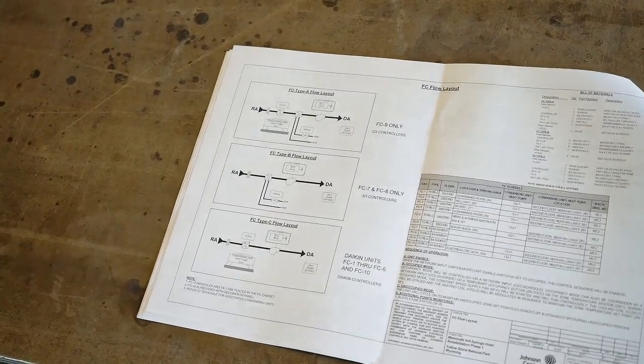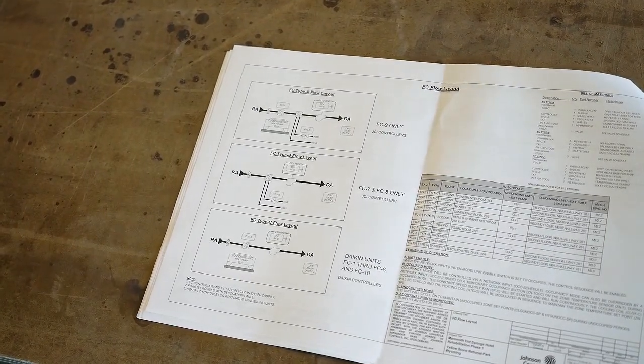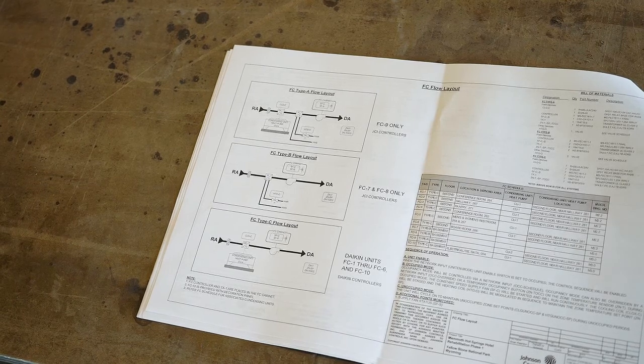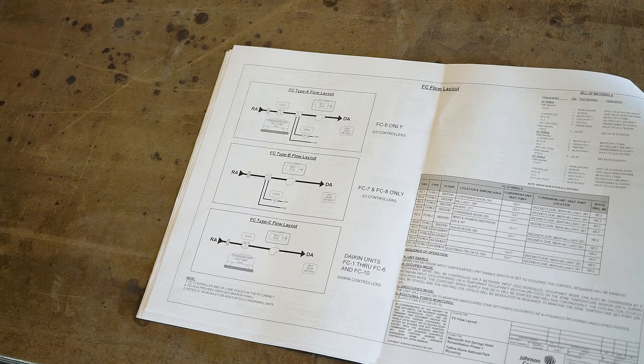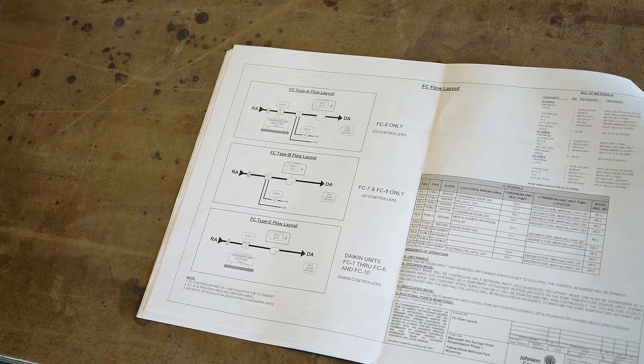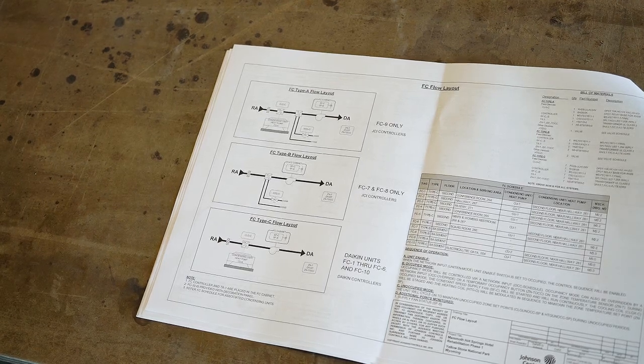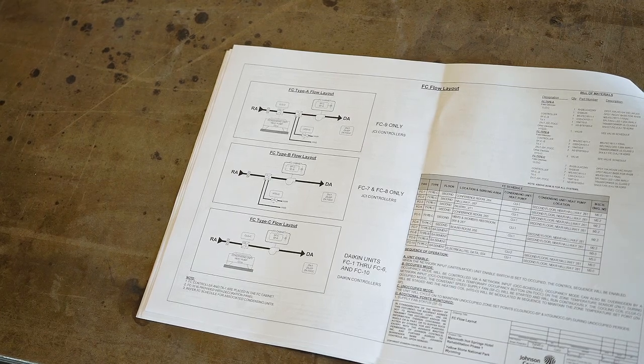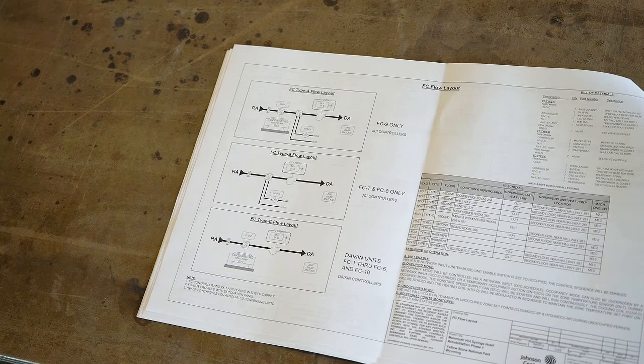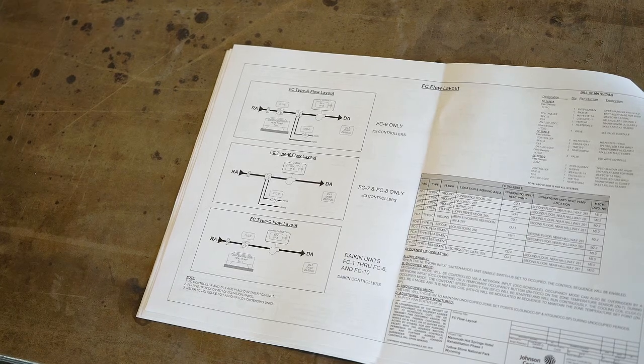So the other thing that we have going on is, I believe right now downstairs, the one in the IT room is set as the master. So whichever one's set as the master is the only one that controls whether you're in heating or cooling. Okay? So that room generates heat, so most of the time that unit's going to be in cooling mode. So that means that these units up here can basically cool only if the master's in cooling.